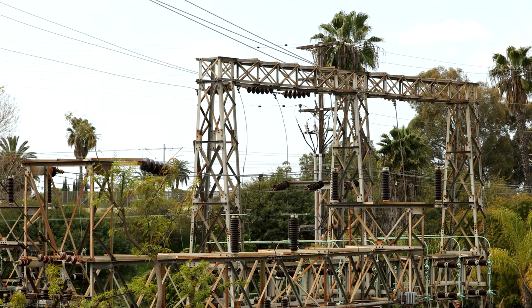A transformer that should have been serviced in May fails in July. A transmission line that should have been upgraded remains at capacity. A substation that was operating at 90% load hits 100% on the hottest day and trips offline, cascading the failure to the next substation in the circuit. That cascade is how a local equipment failure becomes a regional blackout. And the probability of that cascade has increased because the war made everything that prevents it more expensive.